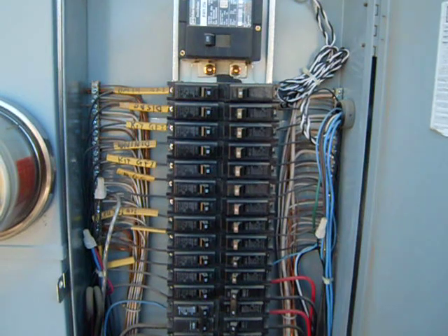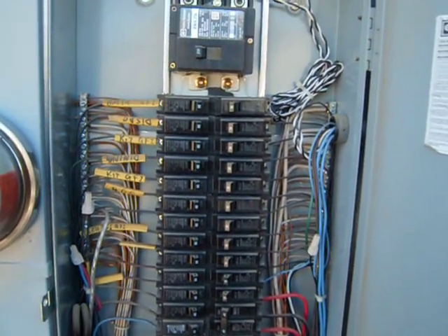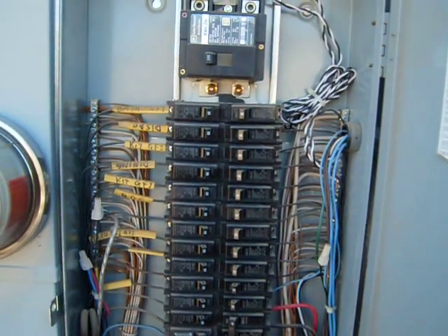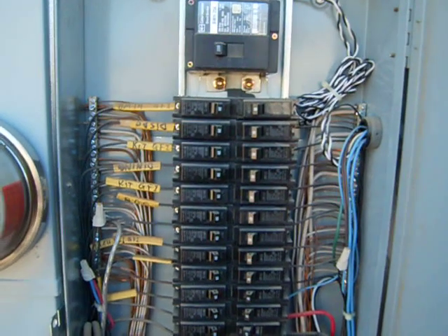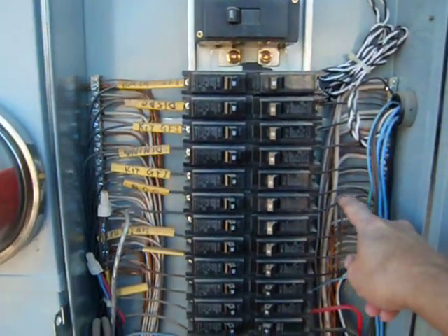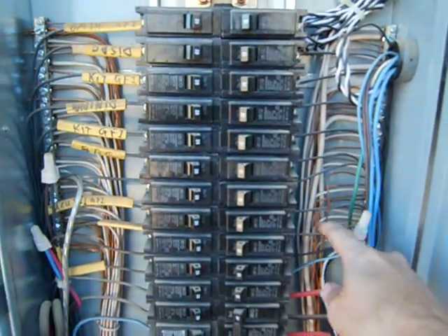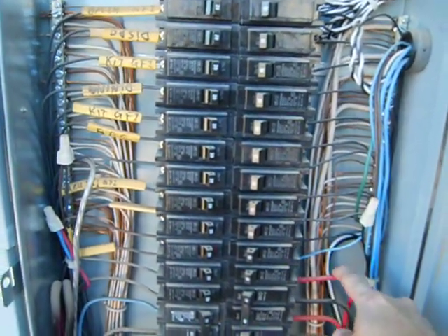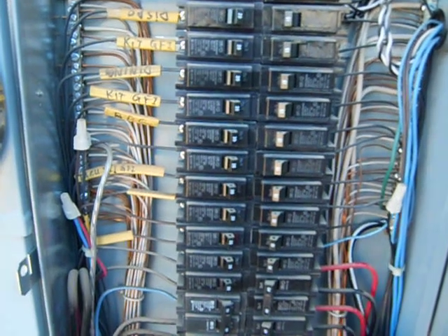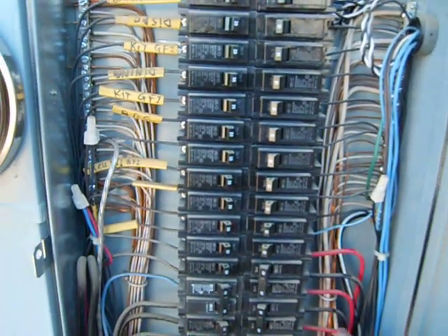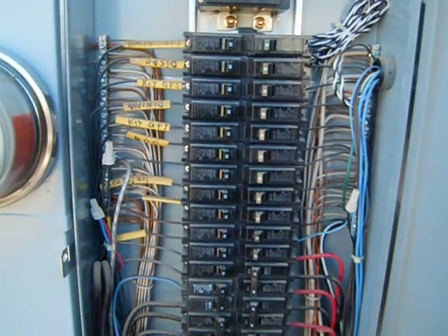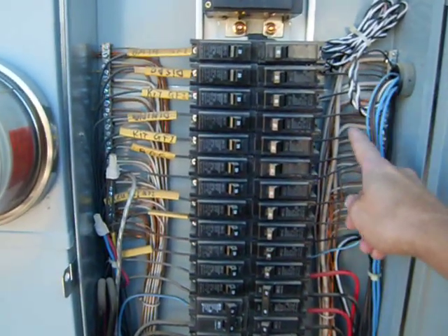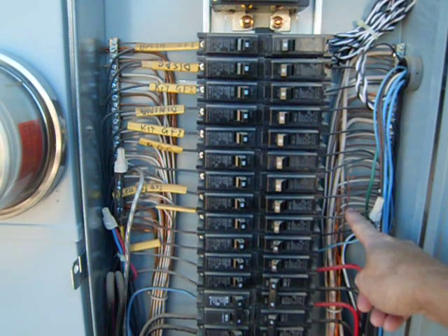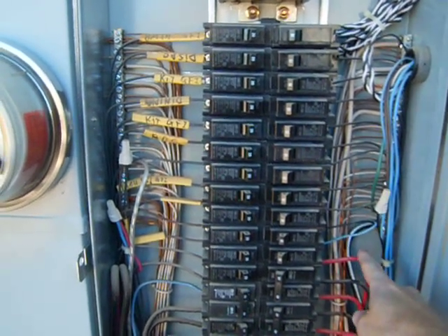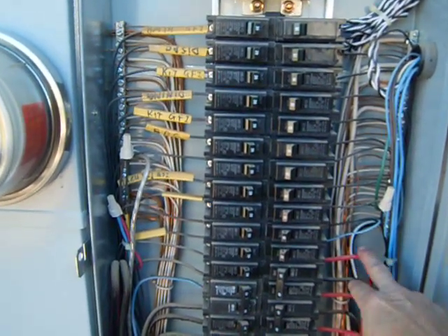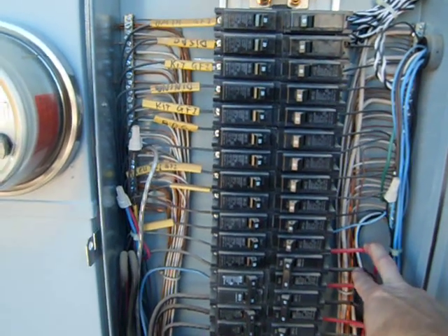Okay, as far as maintenance inside your panel, unless there's a problem, there's not a whole lot you need to do. If you do need to check something, if it's an older house, you're going to look at your power wires coming off each circuit breaker. You might give them a wiggle to check to see that there's tightness and no loose connections. That's going to be the number one cause of a problem in your panel, is a loose connection. So you're going to check your black wires, which are your power wires for your 110 volt. And in the case of your 240 volt, you've got a combination of red and black wires serving those.